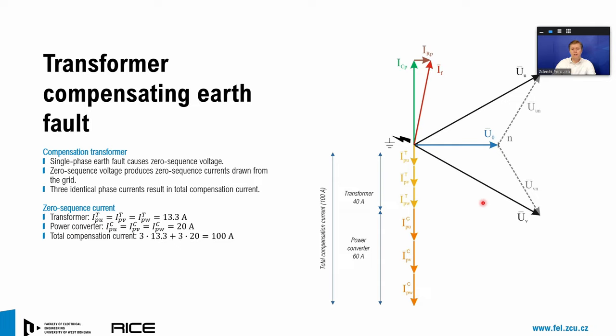So here, this is just for illustration how we are creating the compensation current. If there is an earth fault, there is a fault current IF, this red vector, which we are compensating partially by the transformer. The orange vectors are particular currents generated by particular phases of the transformer. And the remaining part of the compensation current is generated by the converter, which is connected to the secondary winding of our transformer.